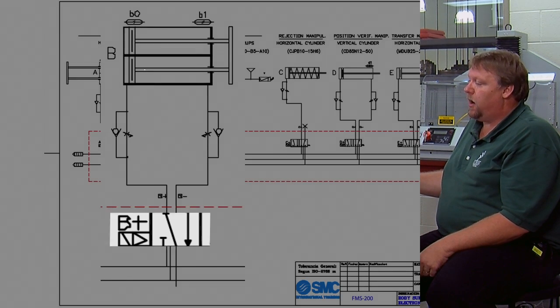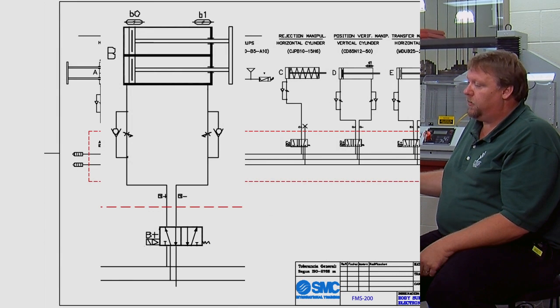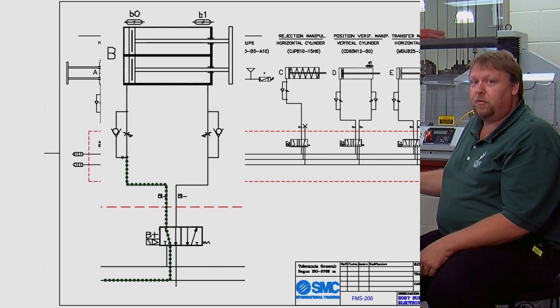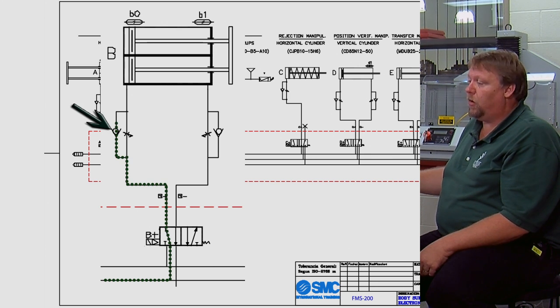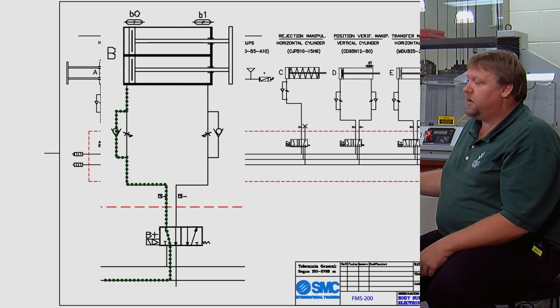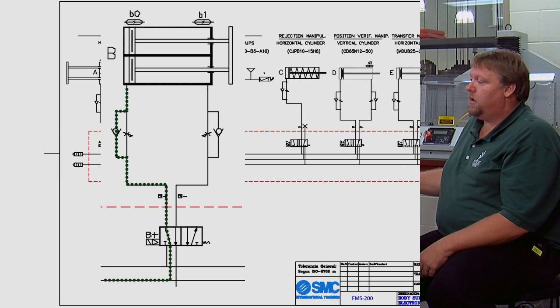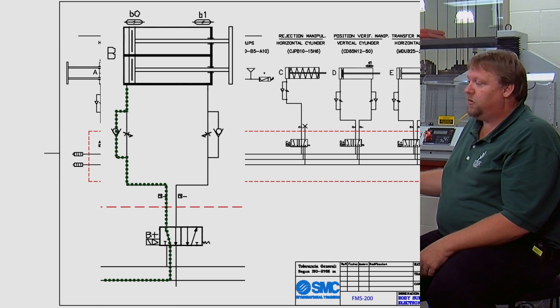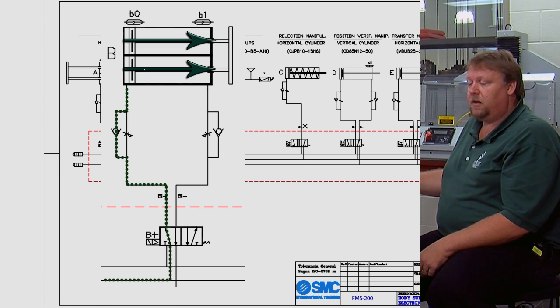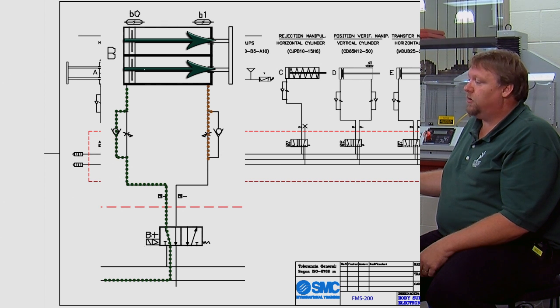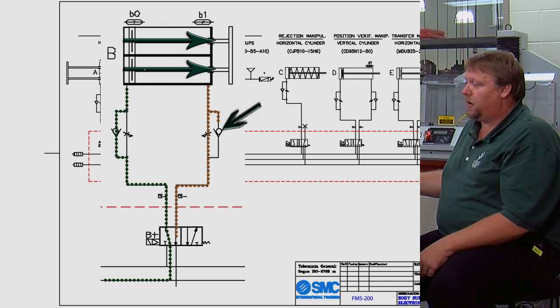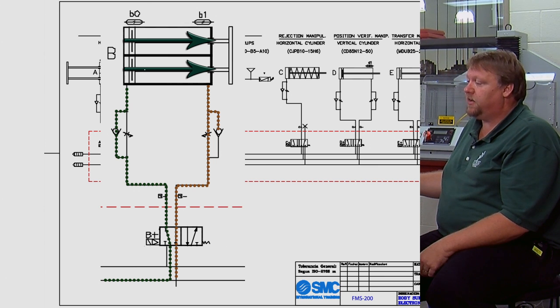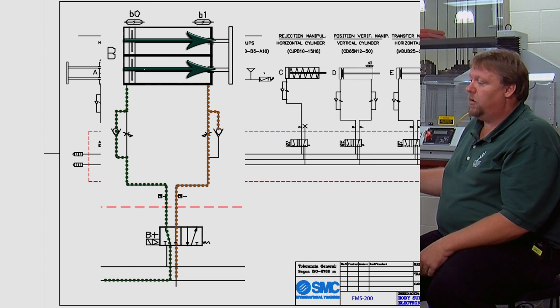So the air would then enter this port. It would go up and it would travel through the flow control blowing the ball off the seat, entering the blank end of the cylinder forcing it to extend. And as it extends all the air is going to be blocked by the ball check valve and then is going to be forced through the metering device again allowing for speed control.